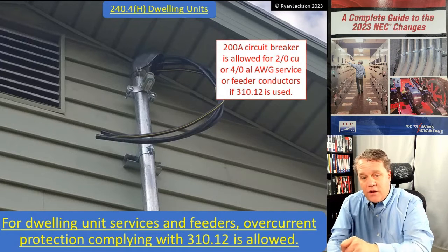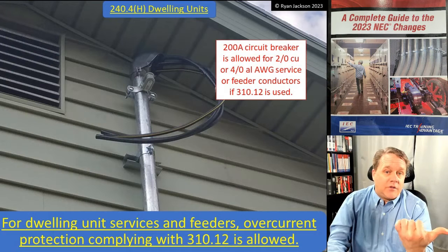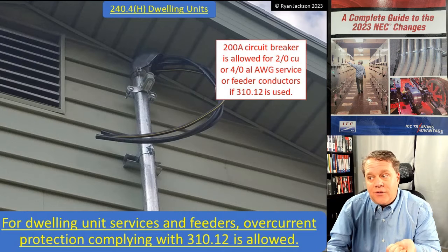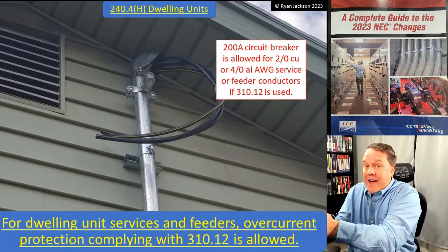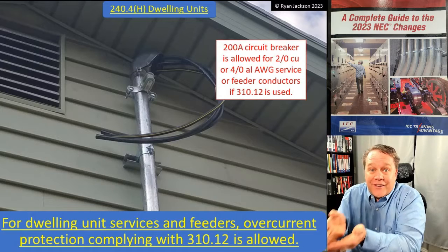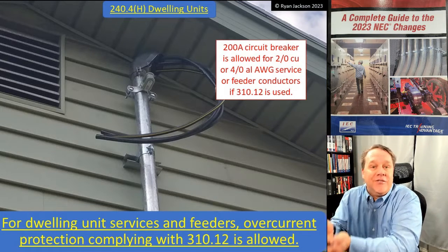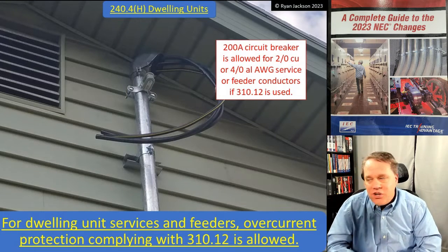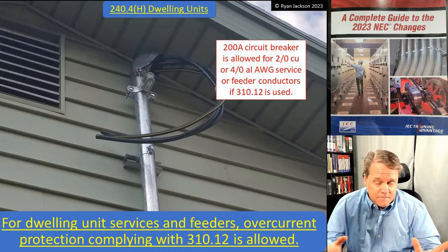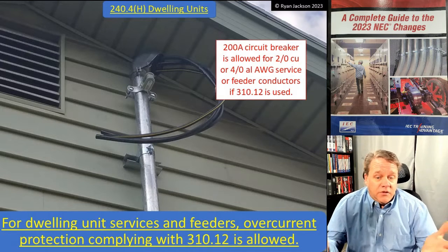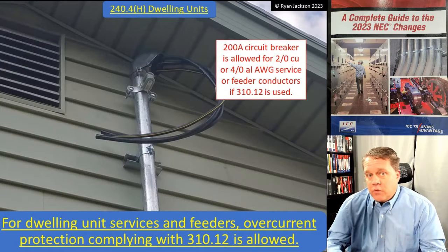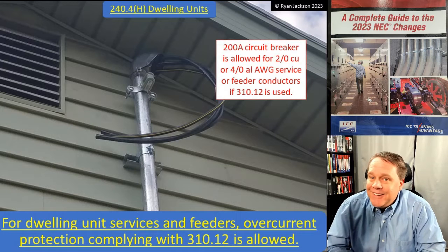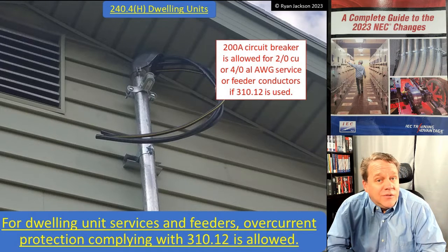Because 310.12 changes the ampacity of those conductors — giving them more ampacity than you'd normally have — going back to 240.4, the conductors are already protected at their ampacity. So 240.4(H) doesn't hurt anything; maybe it removes some field disagreements, but from a code-purist perspective it doesn't really need to be in the NEC. Either way, let's keep going into Article 240 in the next video.